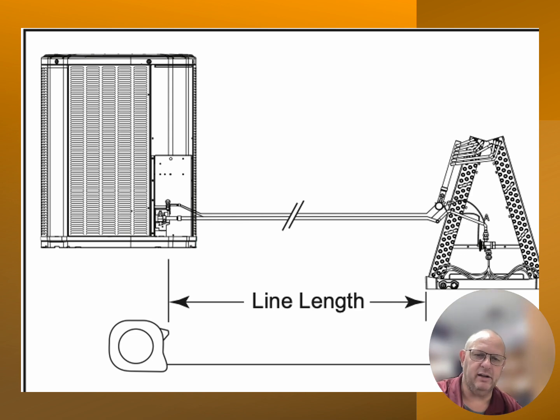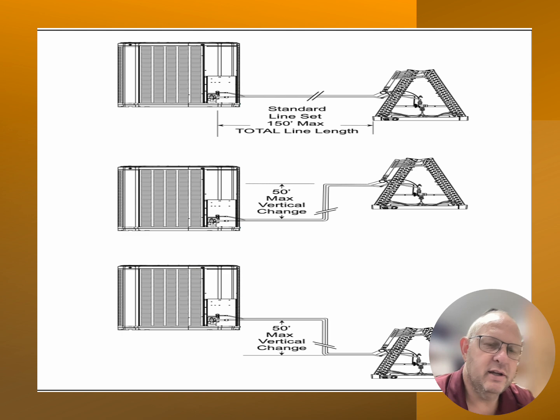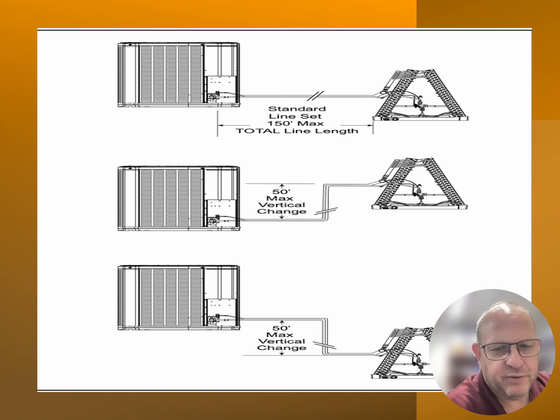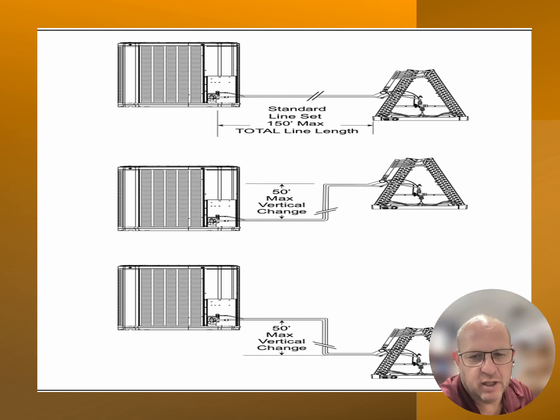Some other things that we have to consider: for this particular unit, and I can't remember if I drew this from a Rheem or a Trane, this particular system has a standard line set of 150 maximum feet that this system can run, with a 50 feet max vertical change of that unit. And if we were going to go down, it has a 50 feet max change going down to the evaporator as well. So you've got to watch for the certain line lengths of this. Now we're going to measure with the tape measure these particular lengths of this line set as we're going with the installation.